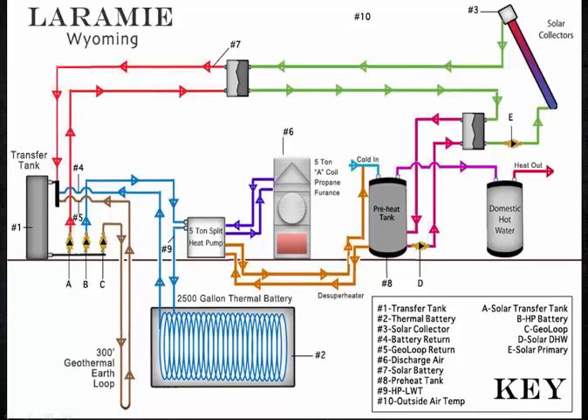Now, the first year we ran it, we had a D circuit coming off of the transfer tank, and we were pumping the heat pump by itself and the thermal battery by itself. We then combined the two the next year because the transfer tank was becoming a pinch point of energy, and although it ran the first year all year long and served the loads, we pulled the transfer tank down into the low 20s a few times, and the heat pump did lock out a couple times and had to be reset.